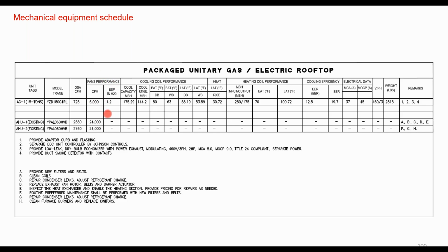And it also doesn't say how the fans are being controlled, right? We don't know if it's a constant speed fan controller or a variable speed fan controller. So that would be something else to understand.